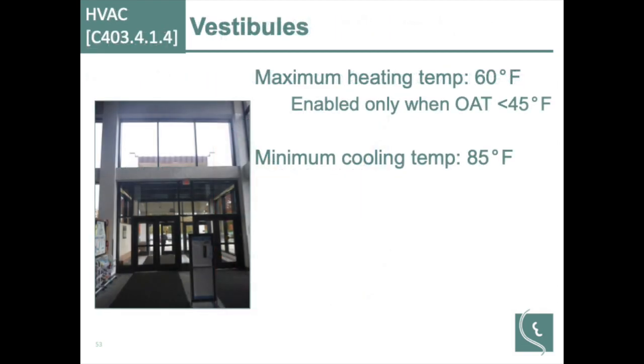Vestibule heating, maximum heating temperature is 60 degrees Fahrenheit, and that heating is only being enabled when outdoor air temperature is less than 45 degrees. Vestibules should be conditioned to interior temperatures. We're kind of getting away from that because that vestibule there has an air break between outside and inside. It's not necessarily a conditioned occupied space. There's no reason to dump all the energy into it to keep it at occupied temperatures. So this code is calling out that space doesn't necessarily have to be conditioned at occupied levels. You can save a lot of energy in those spaces by simply letting them coast a little bit more. So that's a change for vestibules in this version of the code.